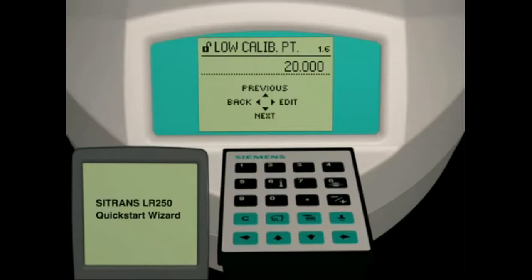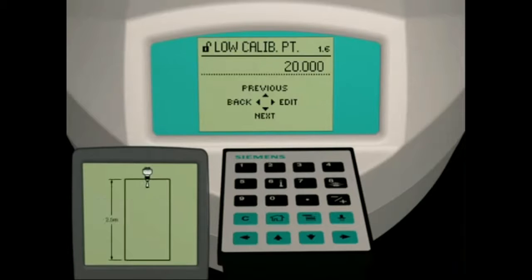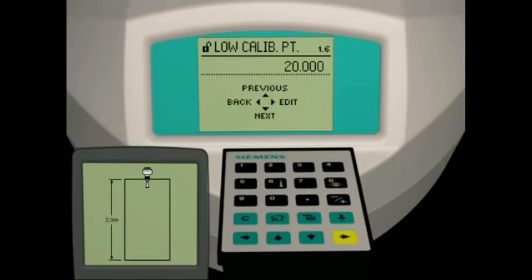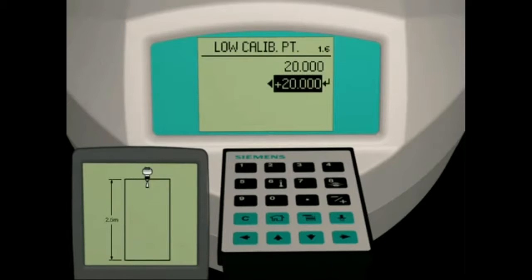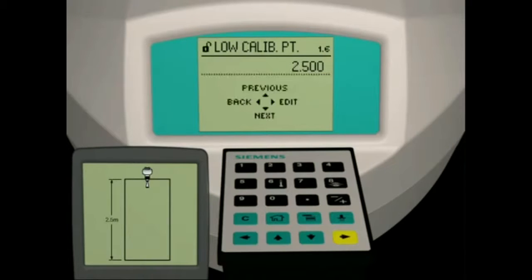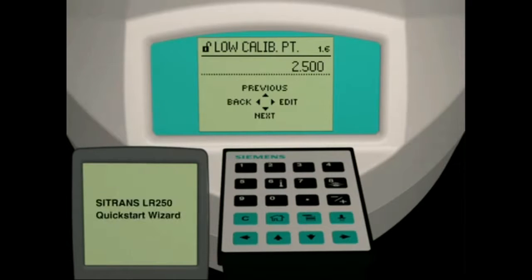Parameter 1.6 is the low calibration point. The low calibration point is the distance from the LR250 reference point to the lowest level of liquid under normal operating conditions. In our application, this distance will be 2.5 meters. Press the right arrow key to enter parameter edit mode, then press 2.5. Press the right arrow key to set this value, then press the down arrow key to move to the next parameter.